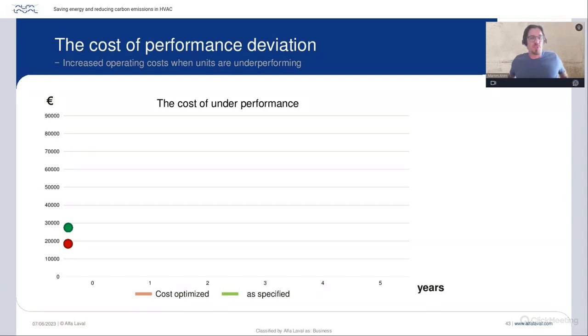So if we look at this from the perspective of operating versus capital investment, the heat exchanger which was sized with market tolerances is the red dot, and the green dot is what was actually specified. In this curve, I've simply added additional operating cost per year. The green line here is when the installation operates as it was intended. There is no additional operating cost because of the higher pressure drop or underperformance of the heat exchanger. But if you look at the cost-optimized unit, the one sized with these market tolerances, as we talked about earlier, it will of course be available on the market at a lower price level for investment cost. But when you look at the yearly consumption of electricity, then you have an additional cost at the operating point.